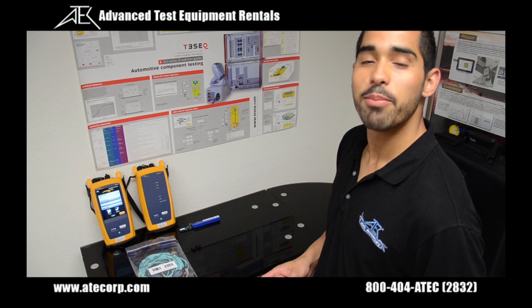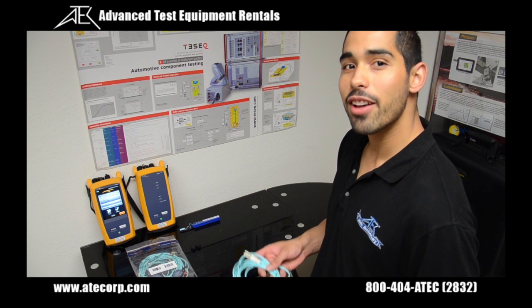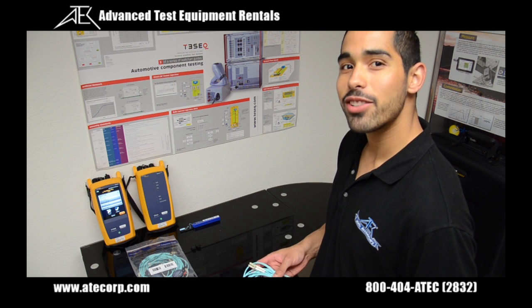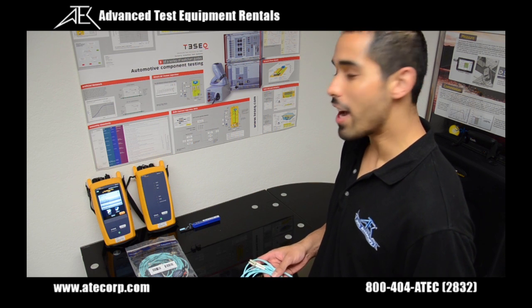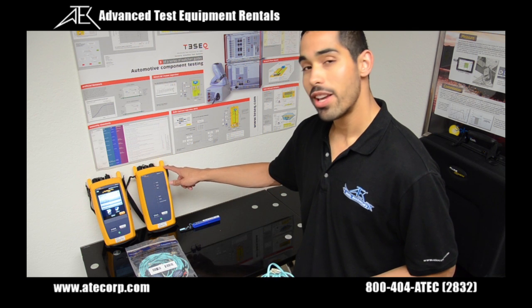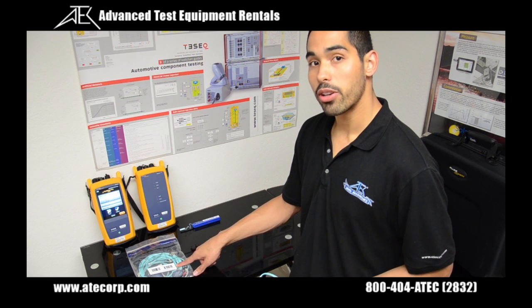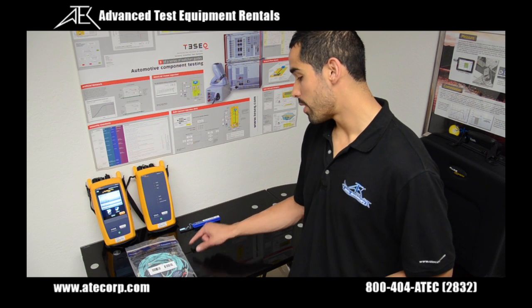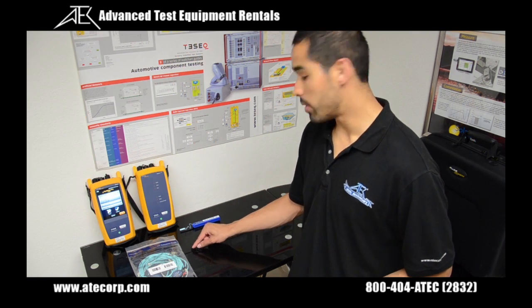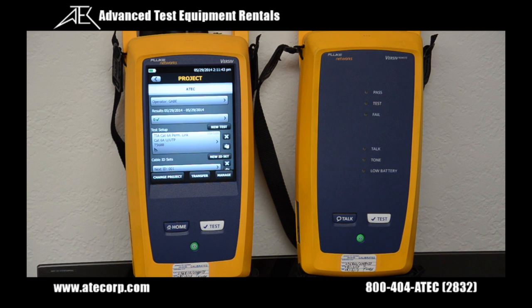The goal for today's demonstration is to fiber certify this 15-foot LC 50 micron multi-mode cable. To do that, I'm going to require both my Versiv mainframe, my remote unit, the CertiFiber Pro modules installed in the rear, my LC 50 micron test reference cord set, two LC duplex couplers, and my fiber optic connector cleaning tool. The first step is to create the test using my main Versiv controller.